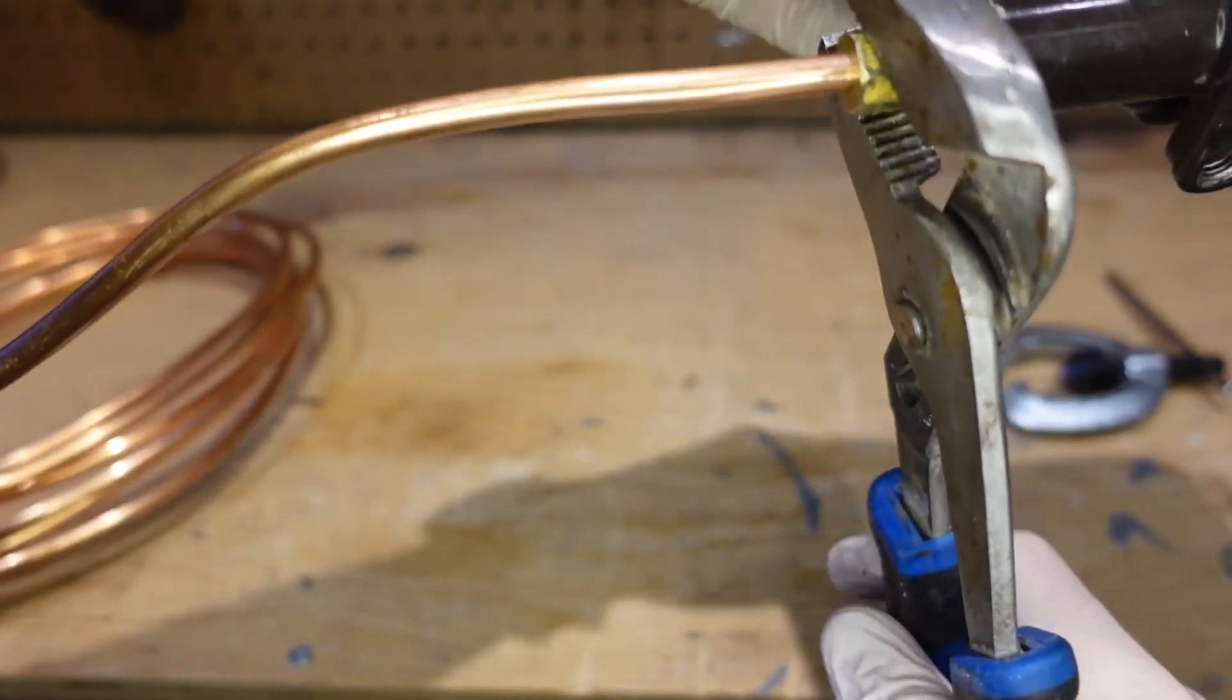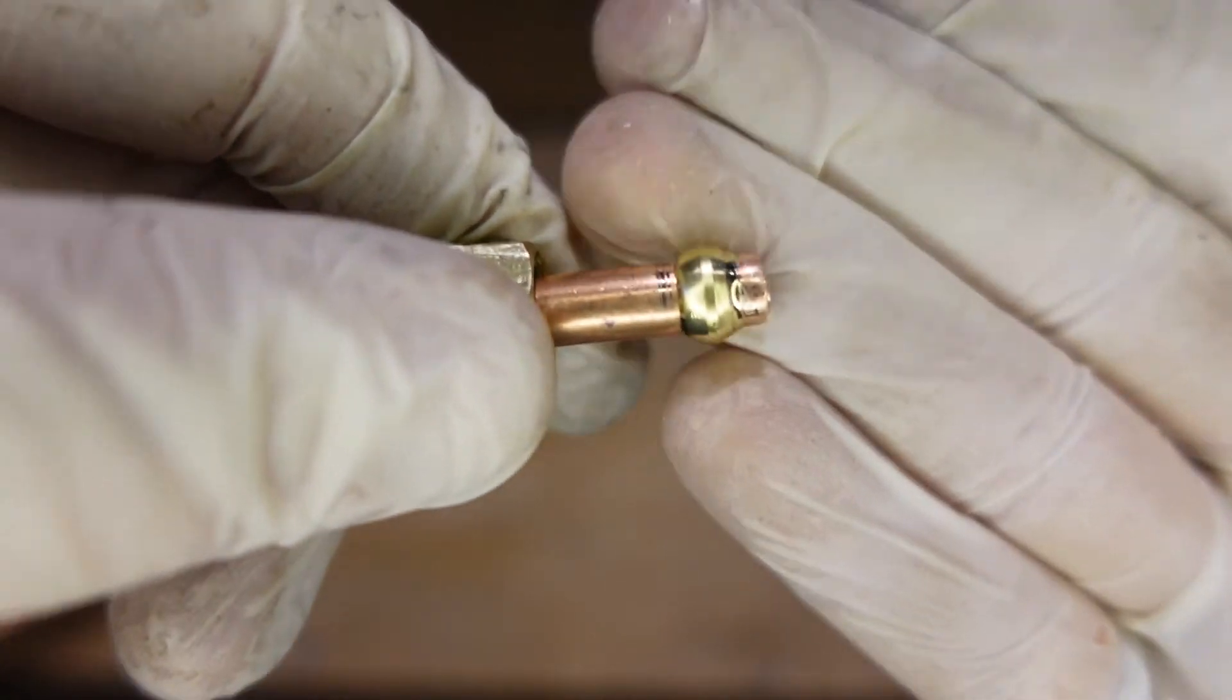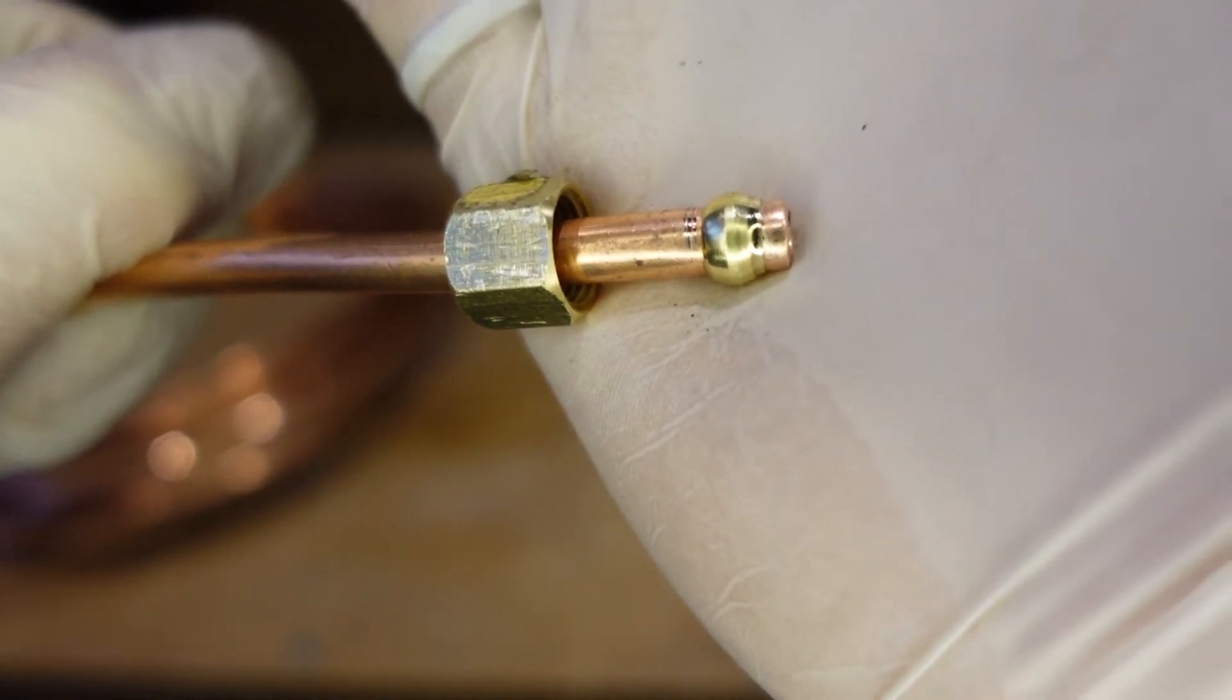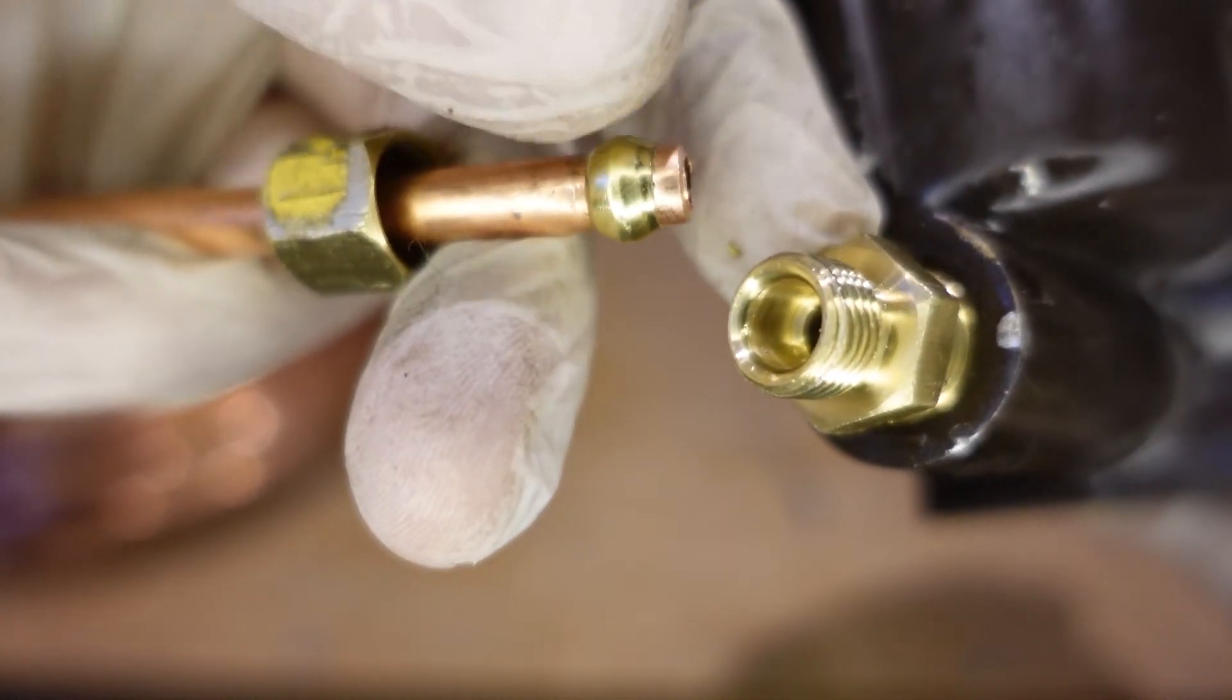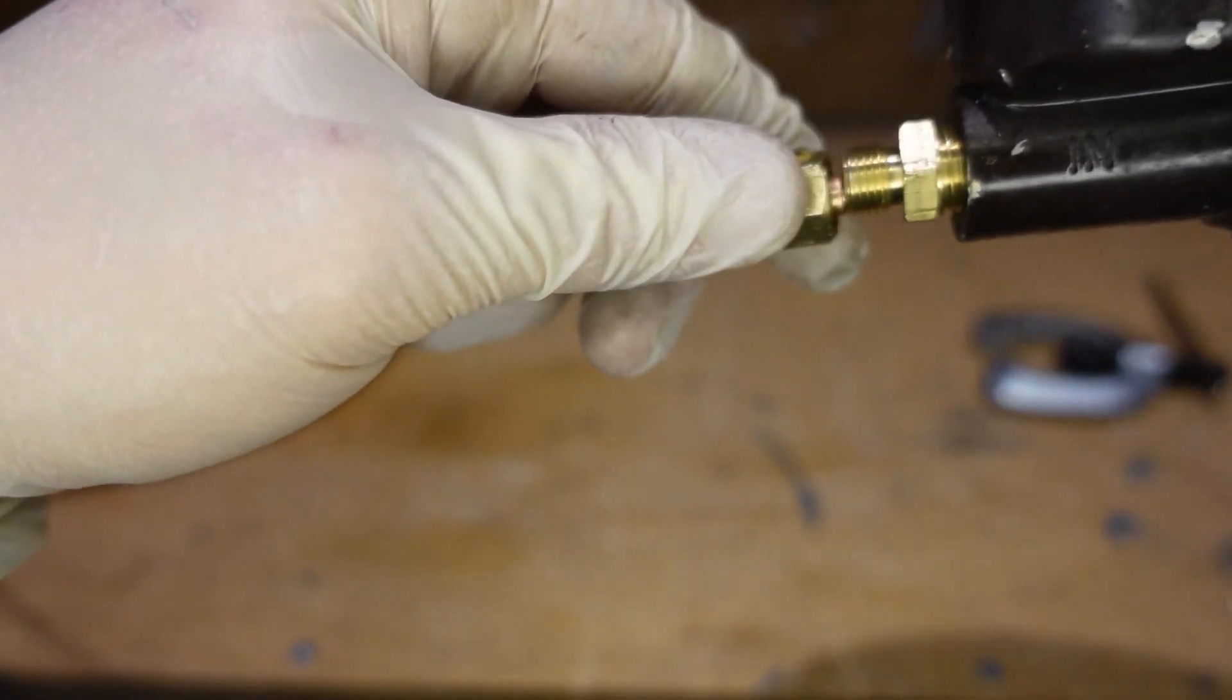We're going to take it apart. And you can see that oil is just from the regulator. You can see the copper tubing is squeezed, that ring came to compress on it so it's snug on there we cannot take it off. When this fitting closes it creates that nice tight gap with the other end of the fitting. You can see inside the fitting here where I'm pointing with my finger it matches the curvature of this ring and the same thing with the other end. This end right here it's curved to match this ring. So when we tighten everything together it is nice and snug.